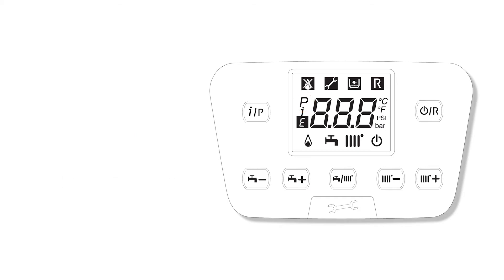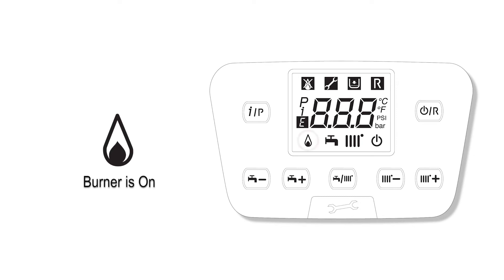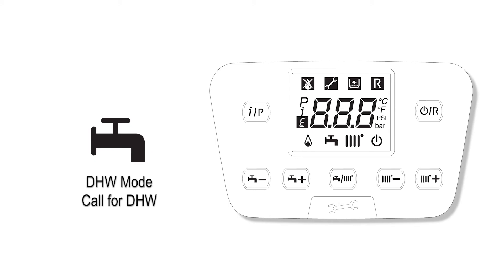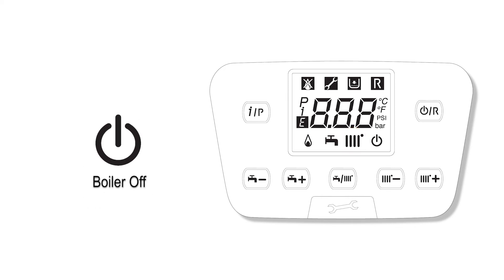The right side of the screen will display Fahrenheit and PSI, the default units out of the box, or Celsius and bar. If the flame icon is on, the burner is lit. If the faucet icon is flashing, there is a call for domestic hot water. And if the radiator icon is flashing, there is a call for central heat. The last icon is the power indicator — if the boiler is off, only this icon will be displayed in the lower right corner of the screen.